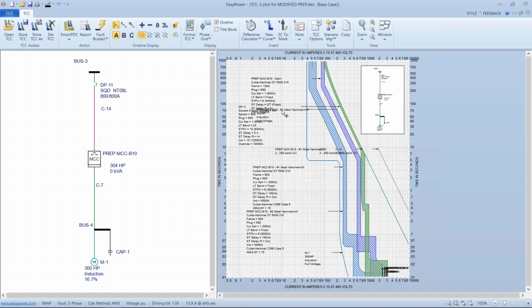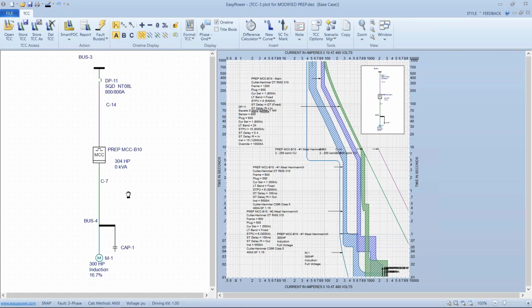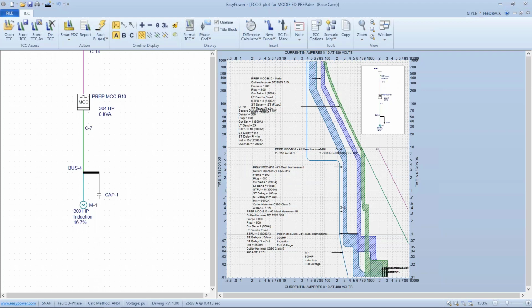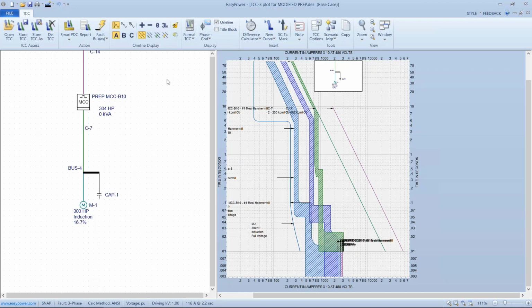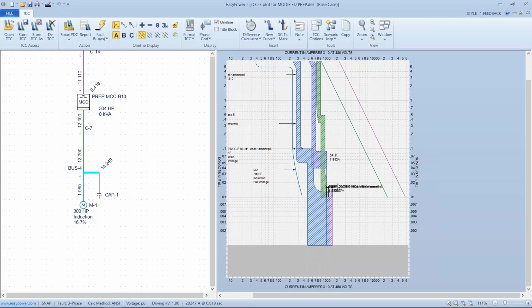Now I have the problem here that I've got two motors with the same starting curve, and they have the same breaker, or a similar breaker. So now if I fault this downstream bus, I can see here that my main current going through that breaker will be tripping at this point, and the next breaker up that it would trip would be the main breaker. And if I want to show the arcing current for this motor, if this bus were to trip, I highlight the curve for that first upstream breaker, right click, and insert the check mark. And this shows me what the arcing current will be.